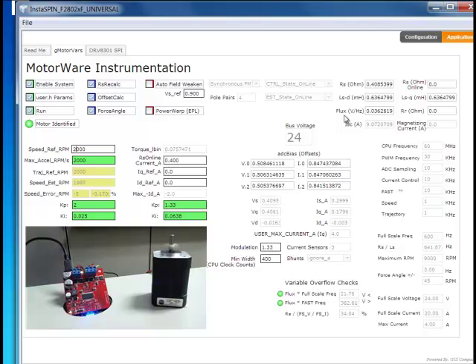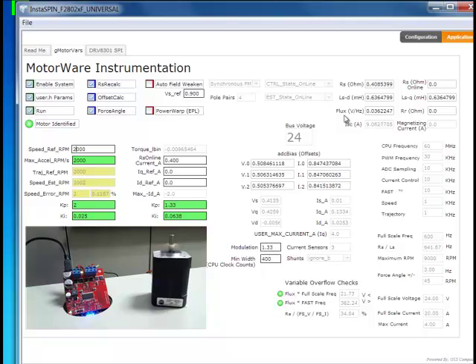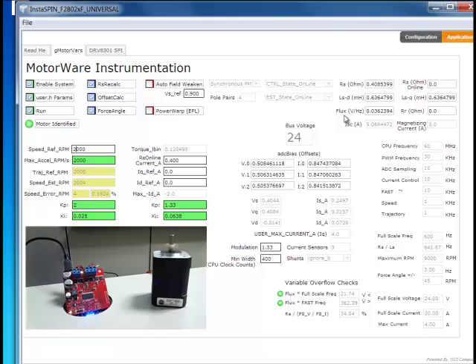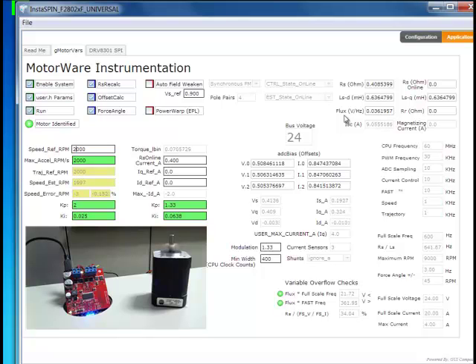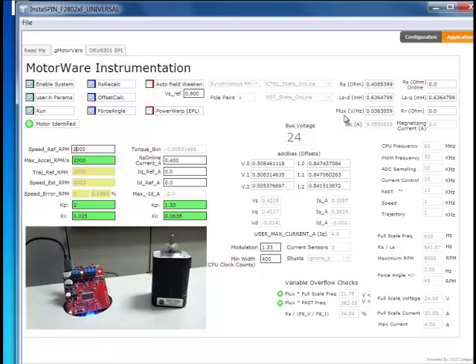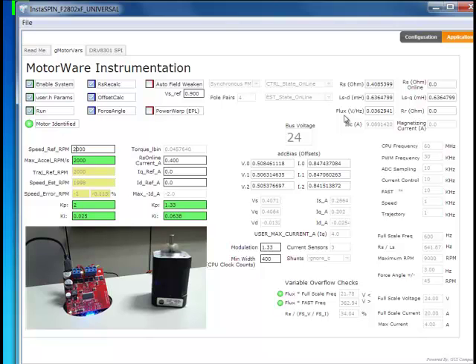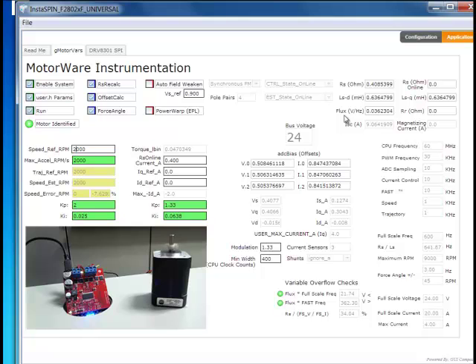This is very useful to properly size a motor. If you only have certain times when you need your motor to go especially fast or over the rated speed, it's a good time to use field weakening. This allows you to use your motor in the most efficient way and choose a motor of the right size for the time that it spins in the most area of its operation at lower speeds and higher torque, and only go to higher speeds with that same sized motor when absolutely necessary. To do that, you have to spend more power. You put more current in and you're going to get a reduction of torque. A good application to think about this for is washing machines, where you need a lot of torque to do agitation with a machine full of water and clothes. But after the water has been taken out of the system, you want to run it very fast to spin the water out of the clothing. This is a very good application for field weakening.